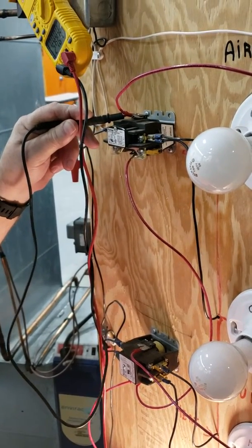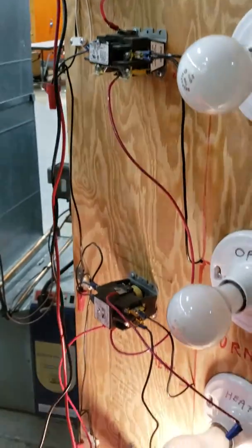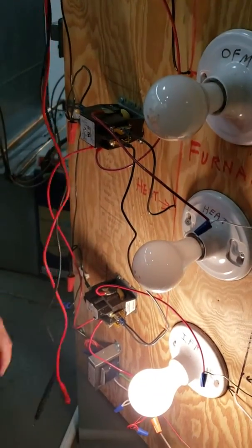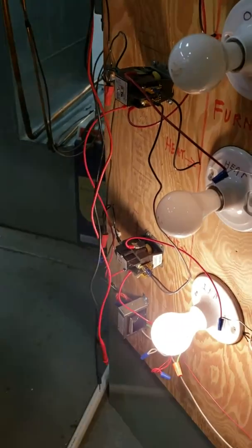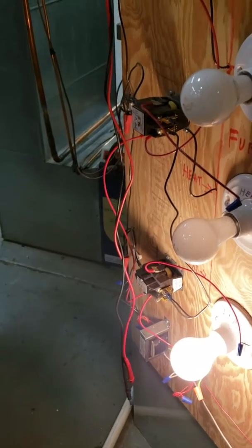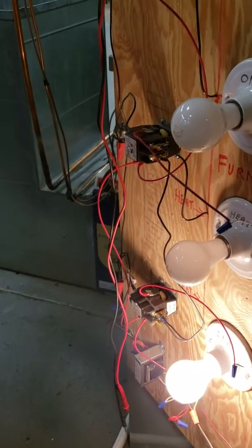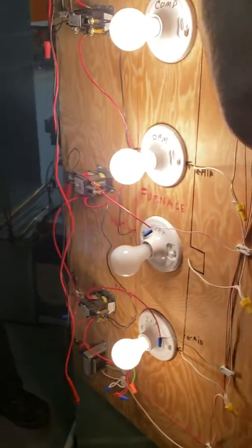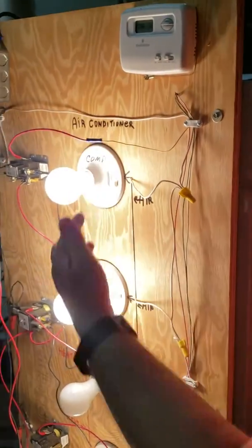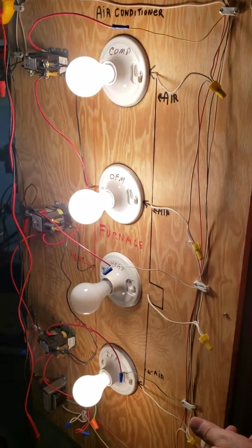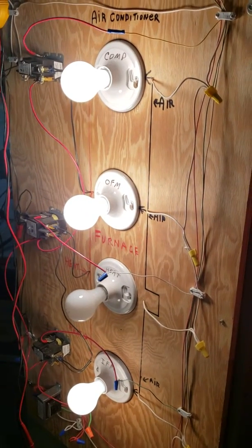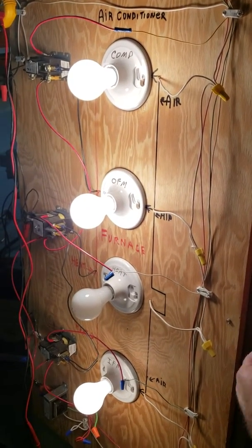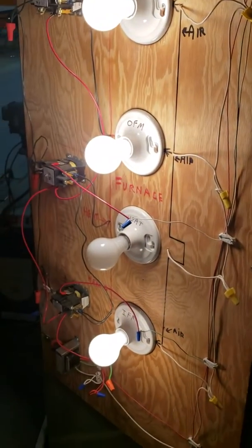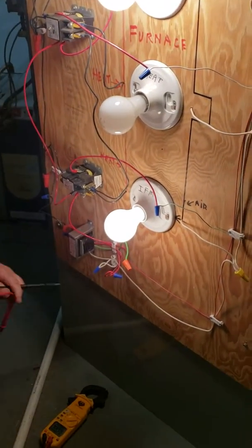What I've done is I've simulated a failure in that thermostat because it had a fuse in the yellow wire, and I just took the fuse out of it. So if I interrupted the circuit here, it comes back out to yellow and feeds over there. So I read voltage across an open circuit right there is what I did. So what do you think I'll read between those same 2 points now? 0.